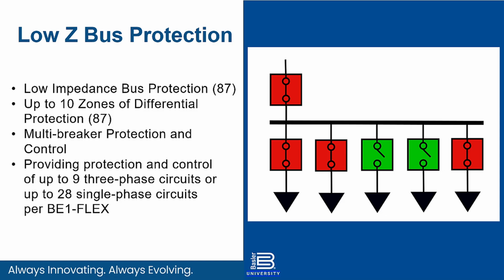We can also monitor bus voltage. With that, we can get power and all sorts of things across all of the feeders. One of the heavy differences and benefits of low impedance instead of high impedance bus protection is that a low impedance protective relay brings all of the current transformer signals directly into the box. And because it does that, it can actually see the currents at each point. A high impedance bus protection application is going to have those current transformers wired together external to the relay, and therefore the relay is only seeing the total and the accumulation of all of those. The downside to that is you can't see individual feeders or individual current transformers, and therefore can't do overcurrent protection and things additional to differential.